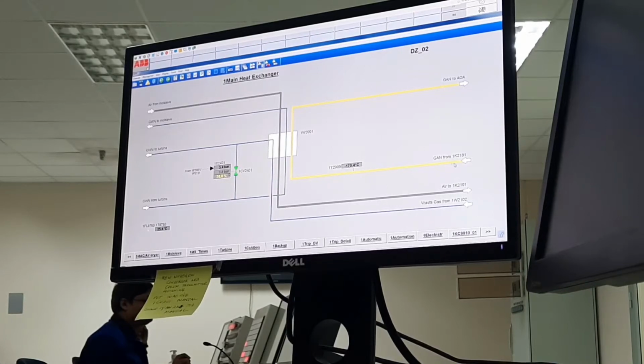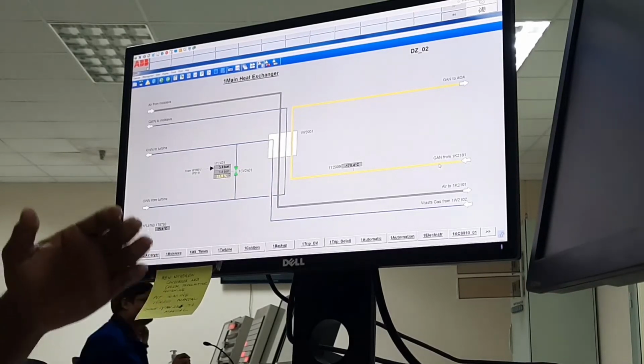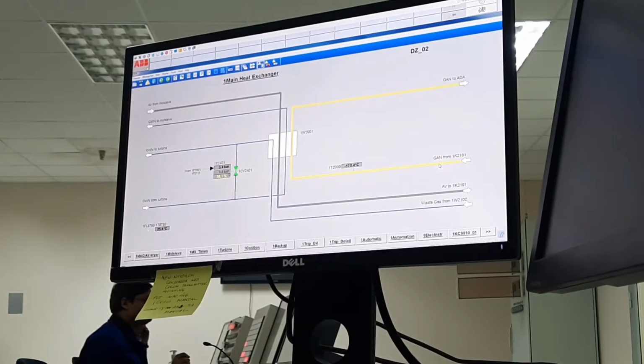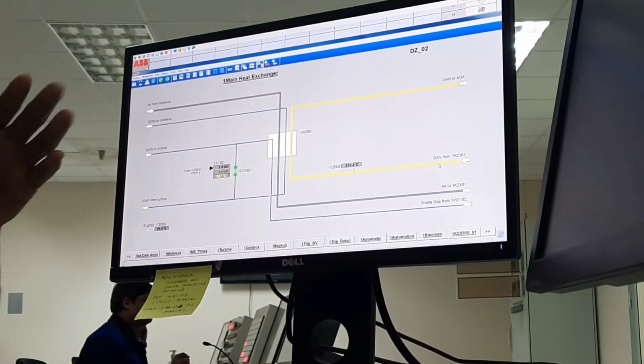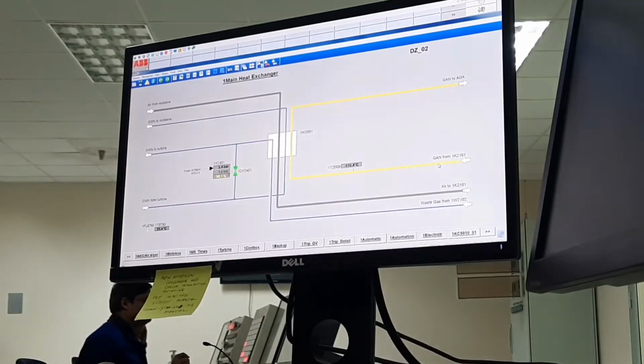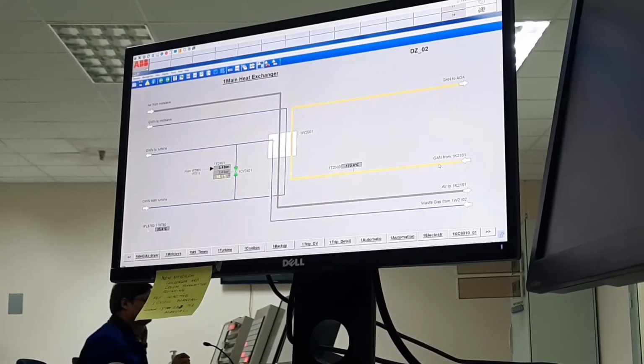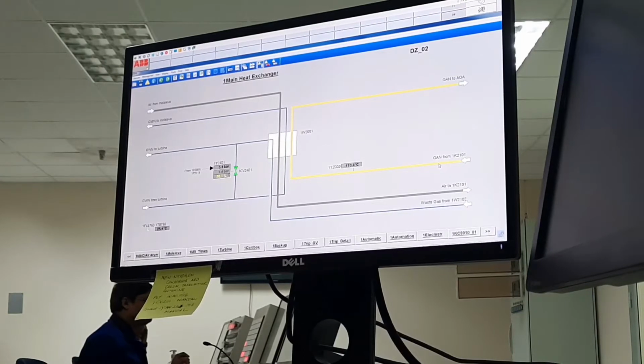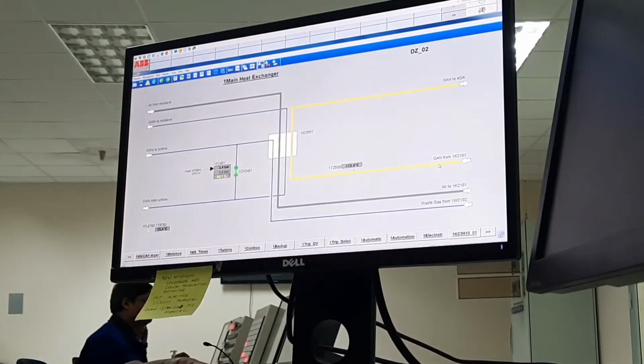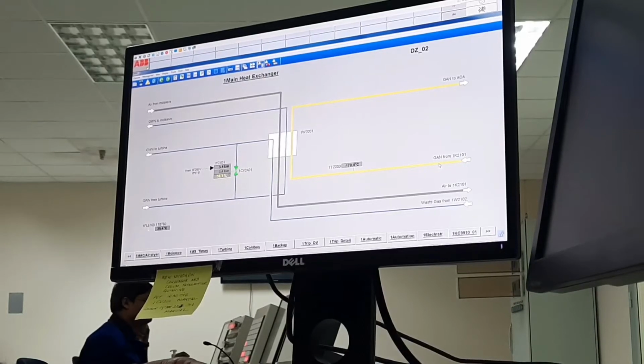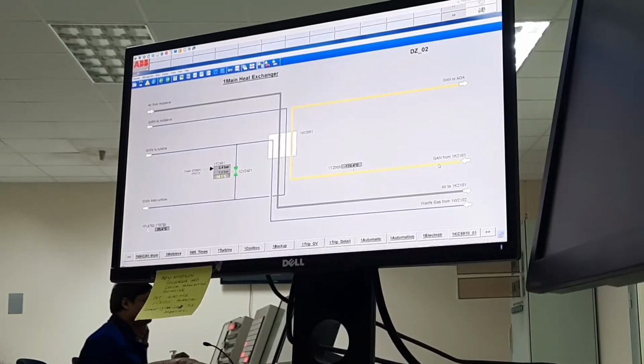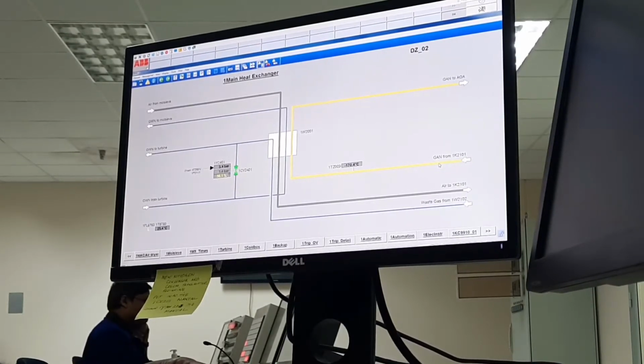Okay, because our gaseous nitrogen product needs a higher temperature. Our gaseous nitrogen product temperature is more than 30. If this is less than minus 170, at that time it is also liquid. So gaseous nitrogen means not liquid nitrogen. Gaseous means this type of temperature. But normally the boiling point of nitrogen is minus 194 degrees centigrade.